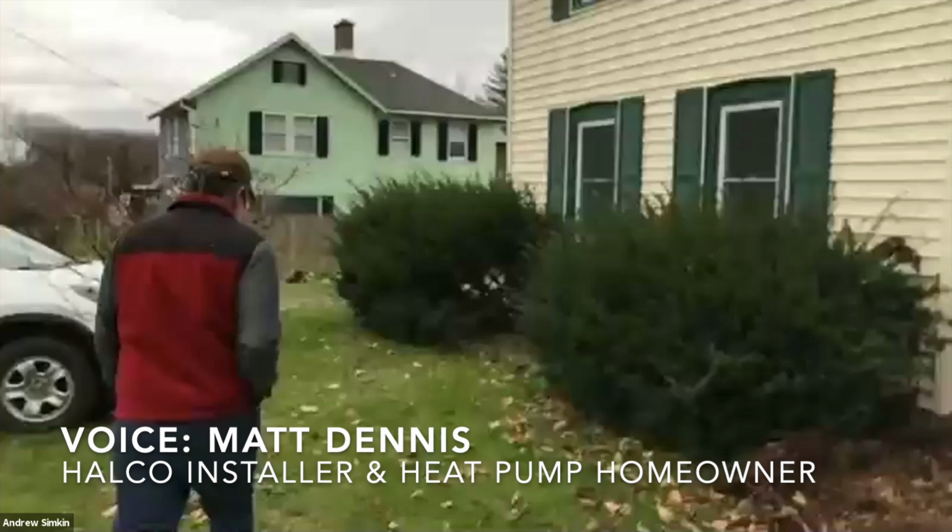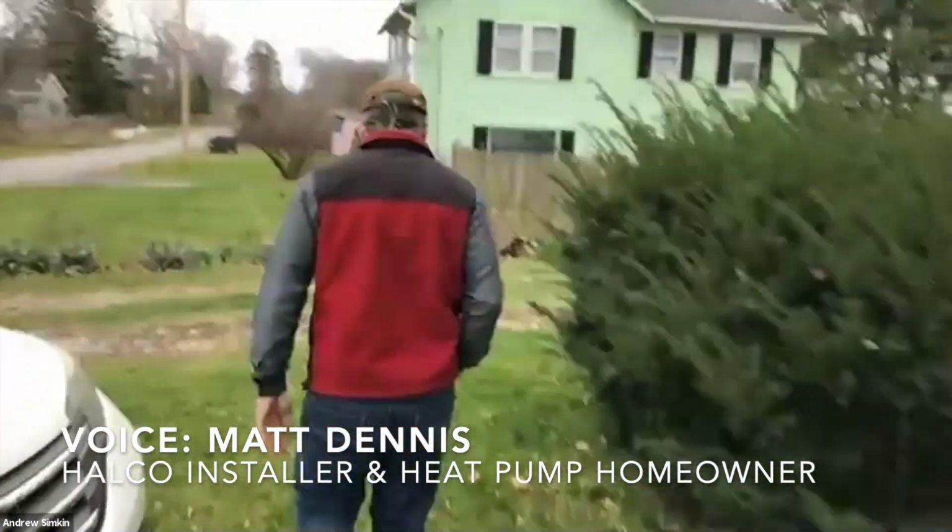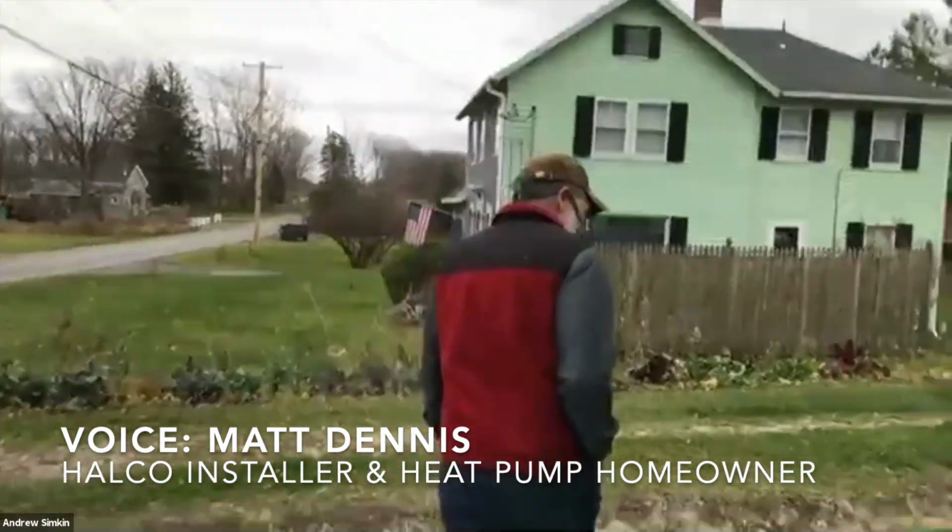You know, in most parts of central New York, it means that once or twice a year, in a big snowstorm, you're going to need to maybe also dig out your air source heat pump as well as your driveway. Certainly, if you're up high in Oswego County where you get 10 feet at a time, you may want to think about having this air source heat pump placed at a higher level. If you know your house and you know you get large snow drifts on one part of the house all the time, well, let's not put something there.